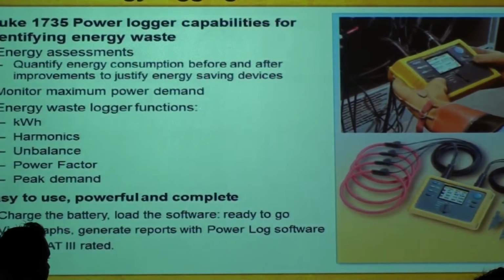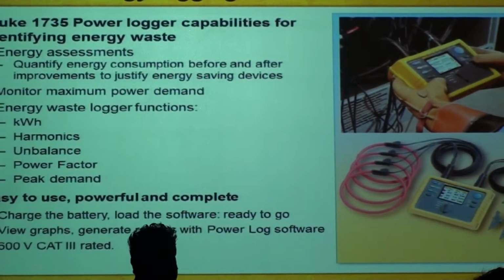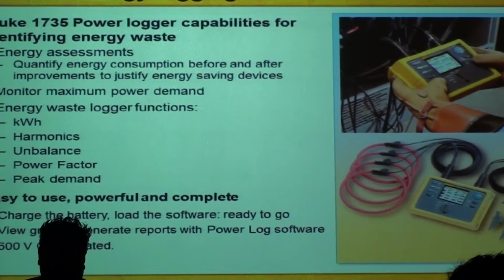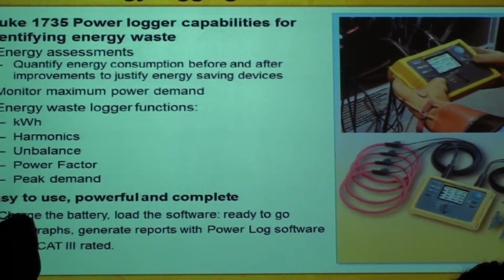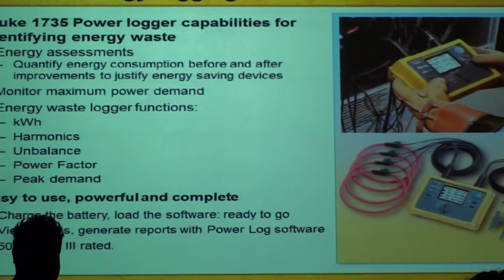A category 4 meter must withstand a transient voltage of 8,000 volts. 8 times on the positive cycle, 8 times on the negative cycle. That's the requirement. 8 times, I'm going to give impulses of 8 kilovolts. And the meter must survive. Not even break, fuse is intact, everything is okay. That's the requirement of category 4. And that's what IEC says.